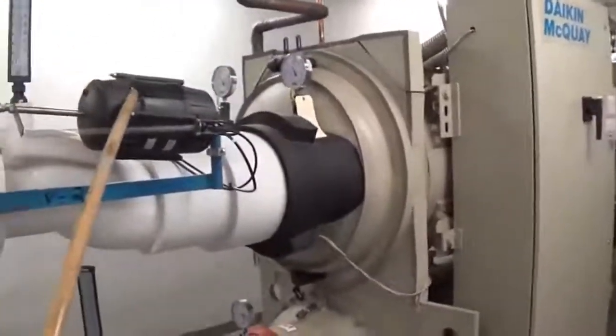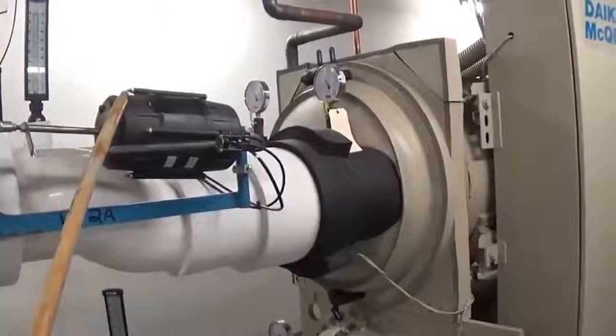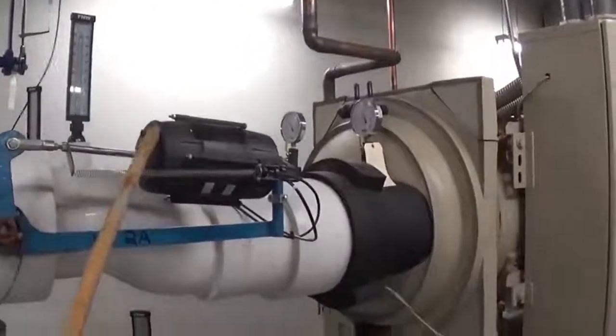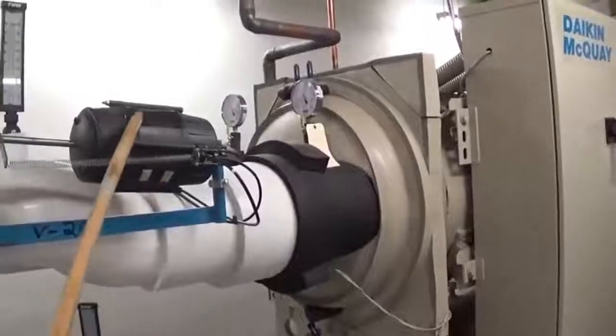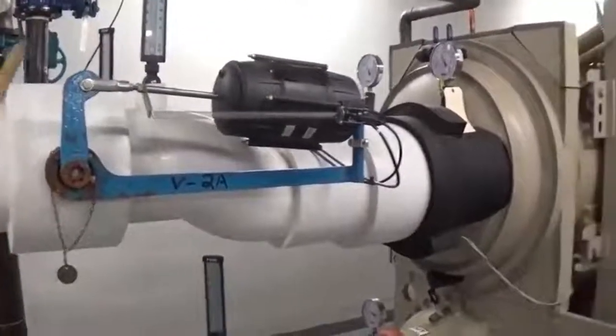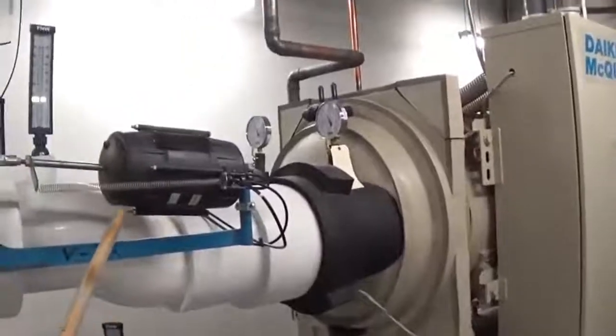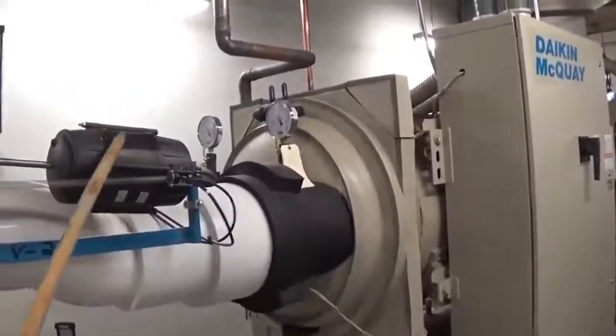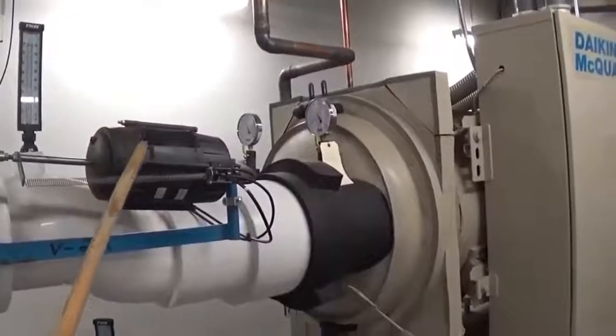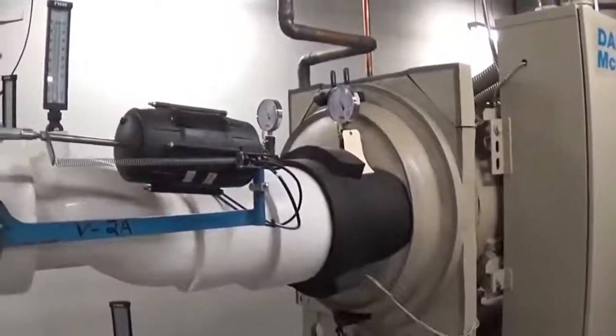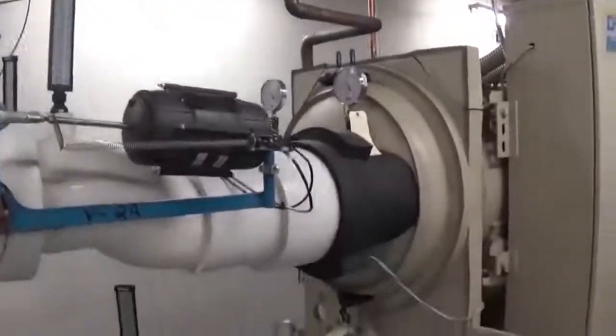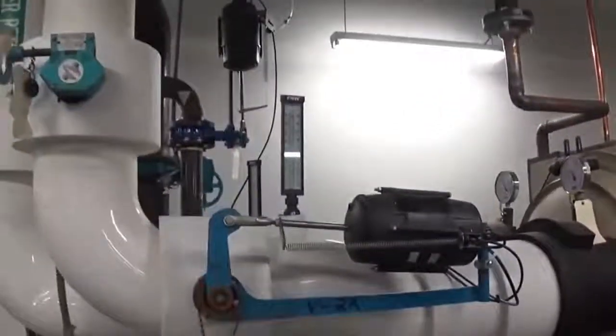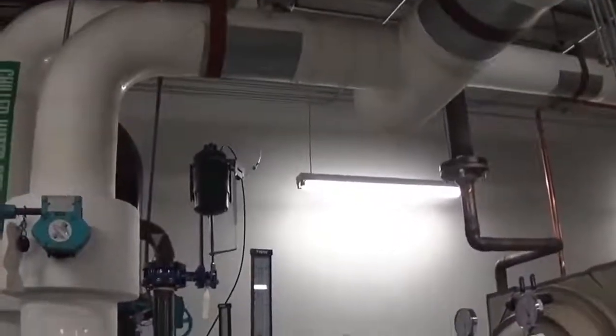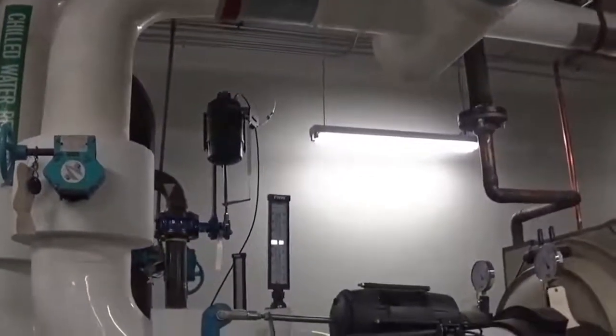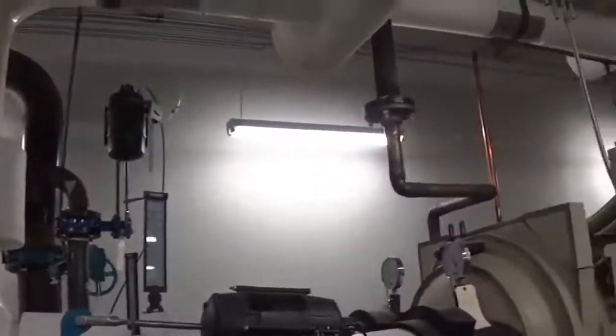When we did the retrofit here, we preferred to keep the old-fashioned pneumatic actuators, which are air valves, or air actuators that operate mechanical valves. They're very, very reliable. They've been here for years. Every couple of years, the crew here will replace the diaphragms or do a little maintenance repair on them, but for the most part, they are very trouble-free. Sometimes the electric valves can be a hassle. So we kept the pneumatics. There was nothing wrong with them, and saved a bundle of money on a retrofit to new valves.